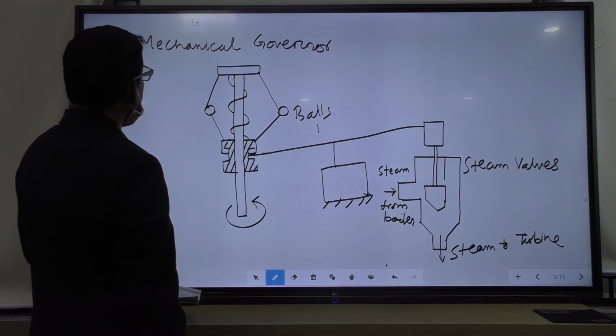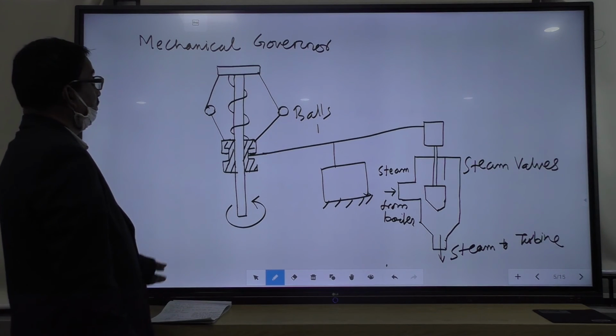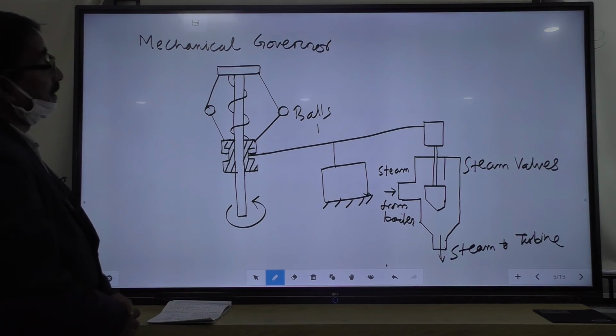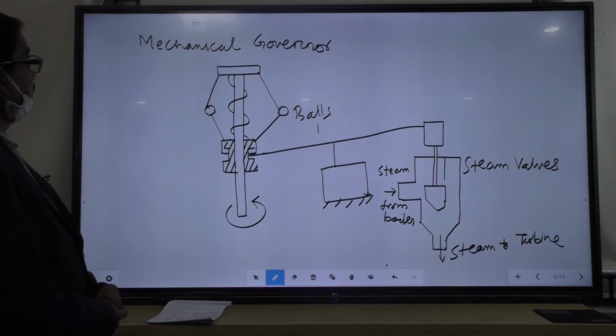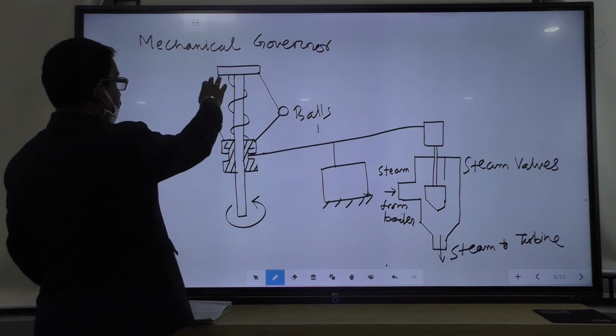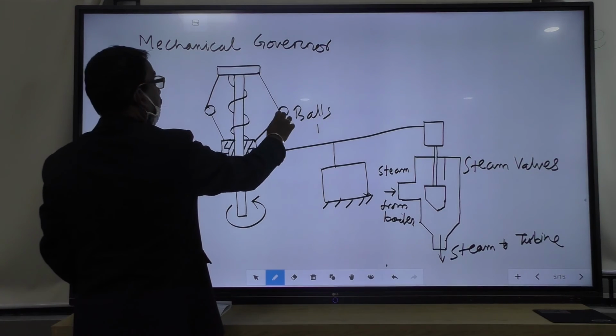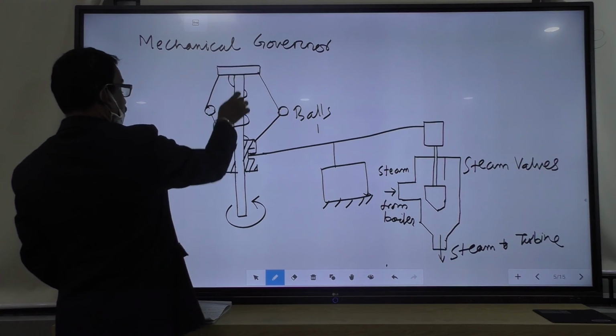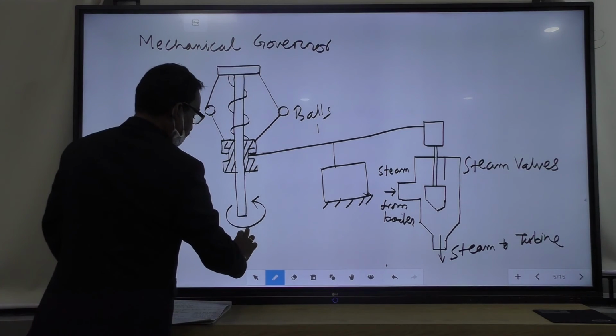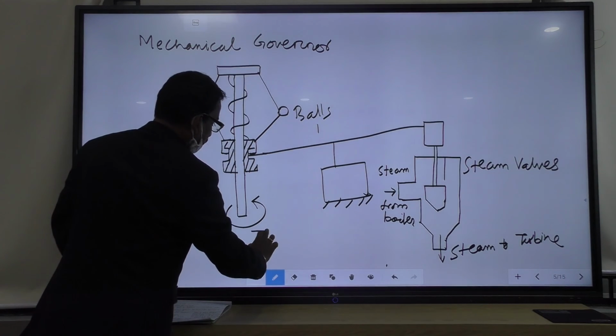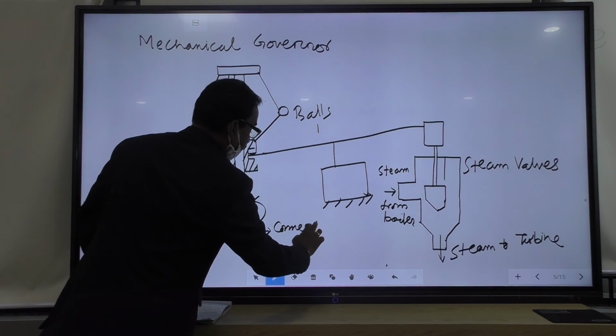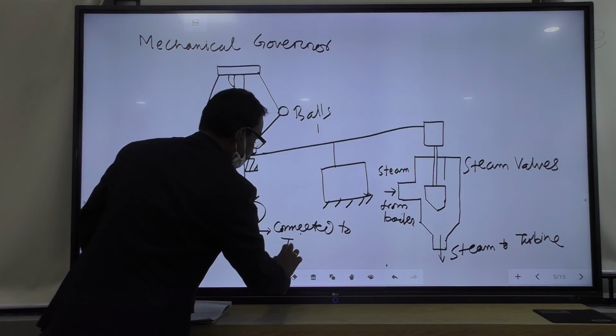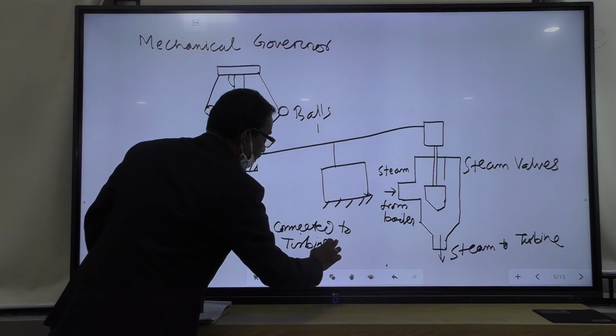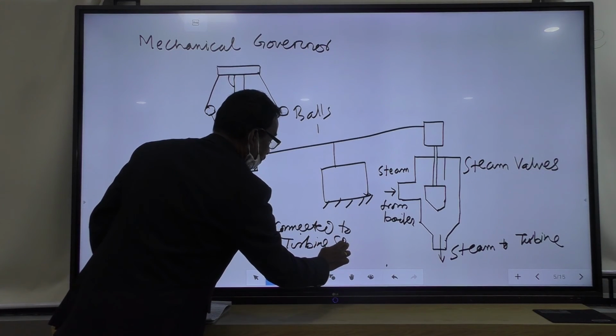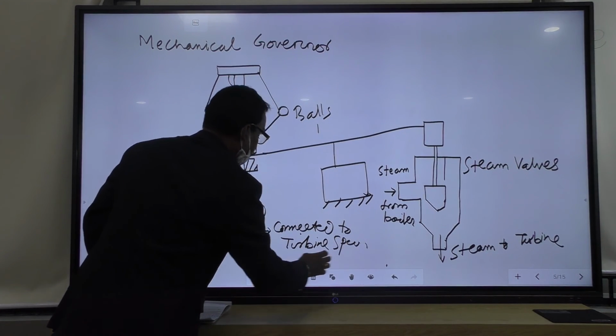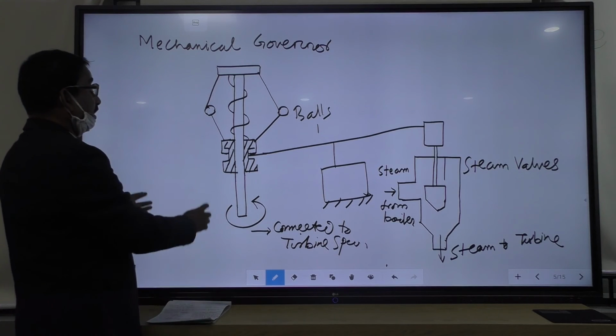This is a spring loaded Hartnell governor which controls the steam flow to the turbine. This is your mechanical governor. These are the different links, the two links, the balls, and this is one rotating shaft, connected to the turbine shaft. The governor shaft is connected to the turbine shaft, that means it is getting power from the turbine shaft. That means the speed of the turbine can be sensed by this mechanical governor.